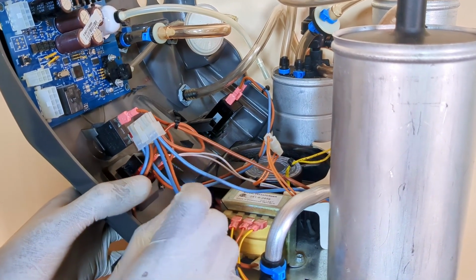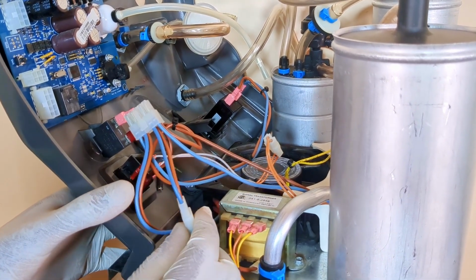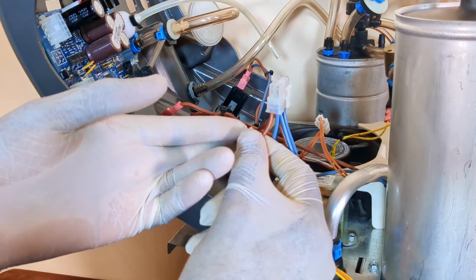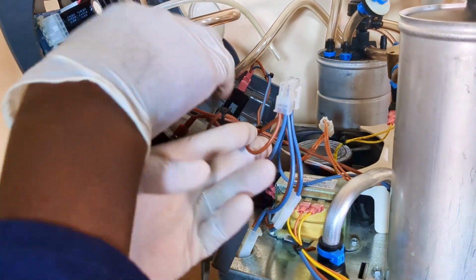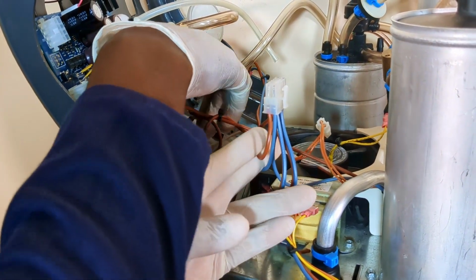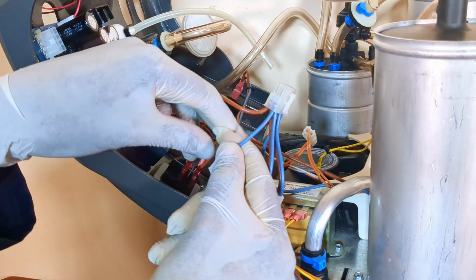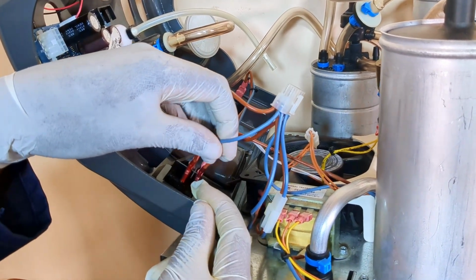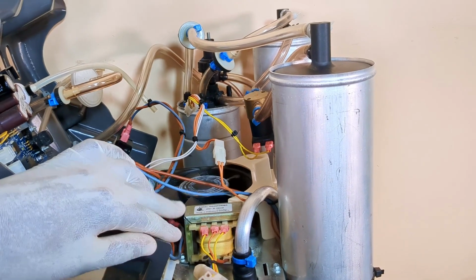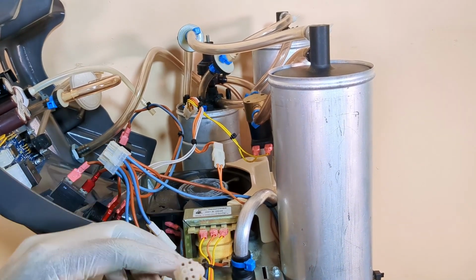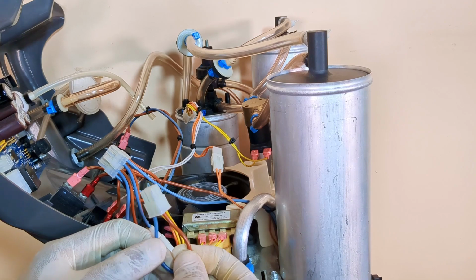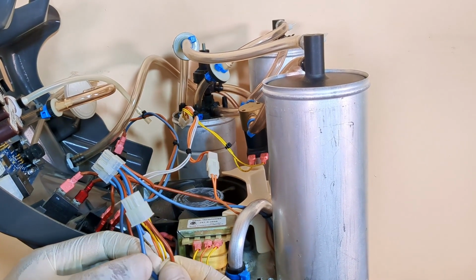Now from the AC output pins, the cooling fan is supplied with 120 volts AC through this live cable, with the blue one being neutral to the fan. This 120 volts AC is also supplied to the hour meter through this live cable, with this blue one being the neutral to the hour meter. The input side of the transformer is also supplied with 120 volts AC through this live cable, with this blue cable being the neutral.